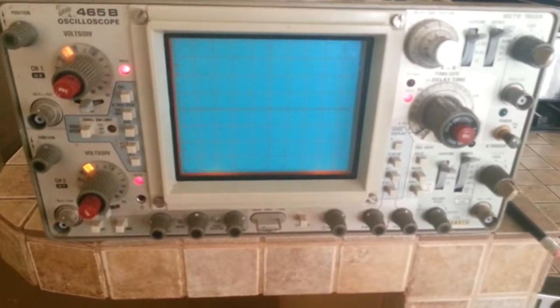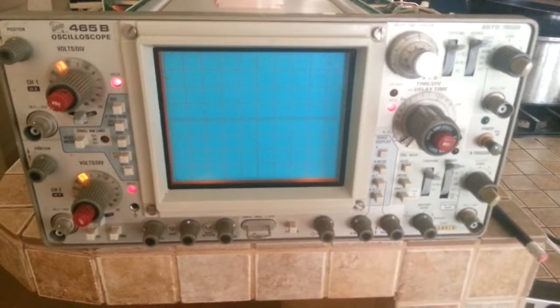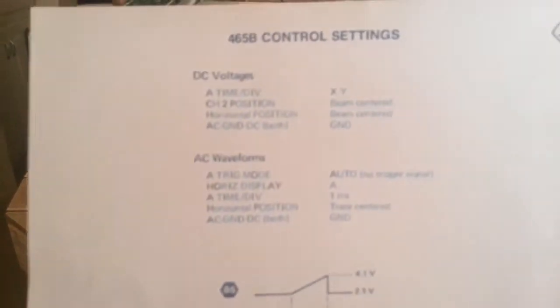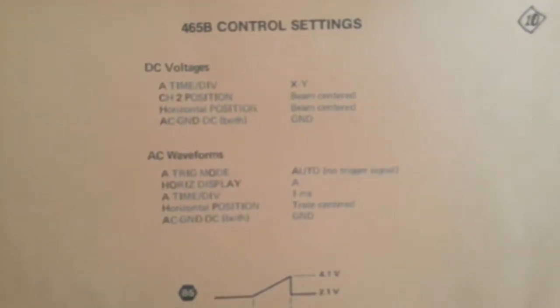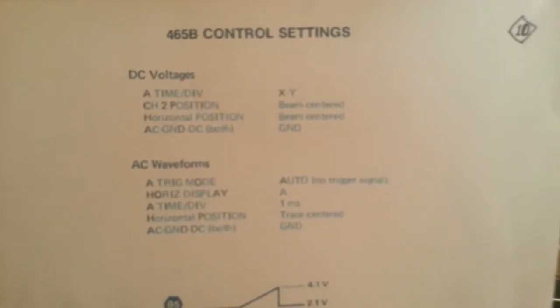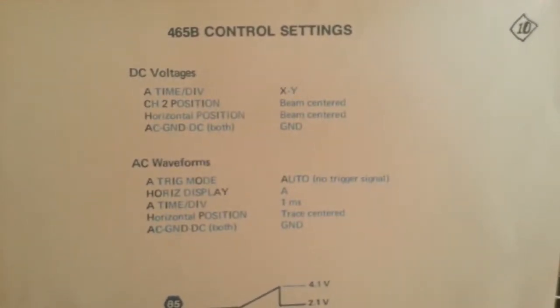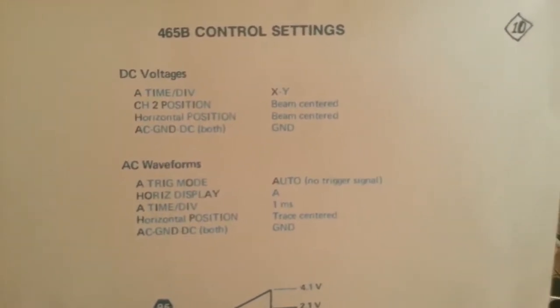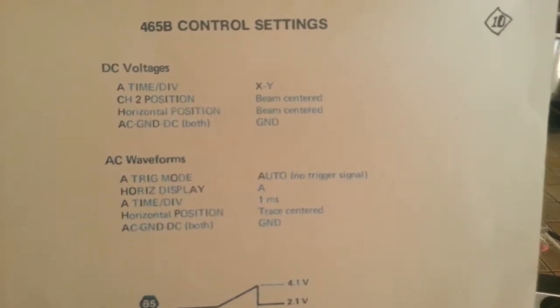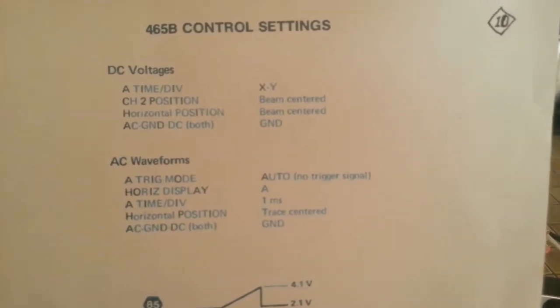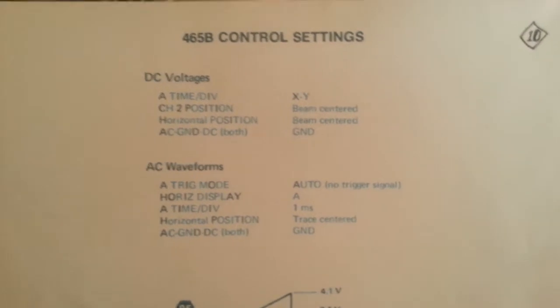On this 465B oscilloscope, I've now set the control settings as you see in the upper right-hand corner. This is for schematic 10, which is the horizontal amplifier. I have it all set up to these settings from the Tektronix service manual.